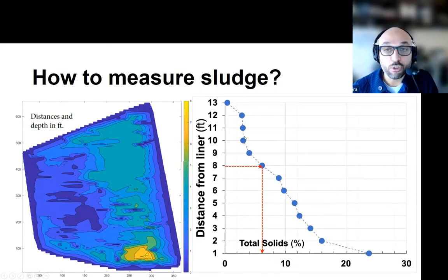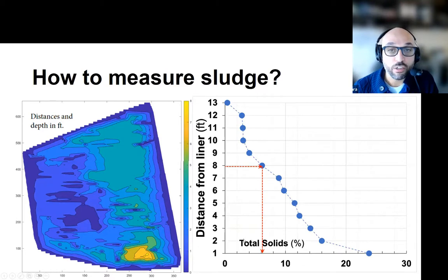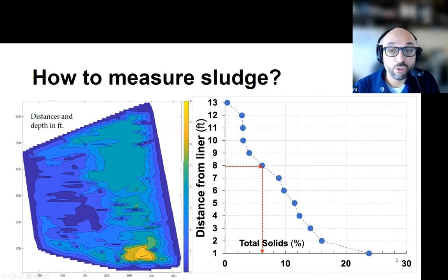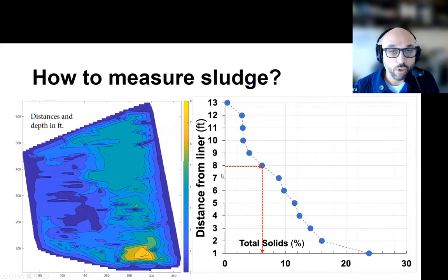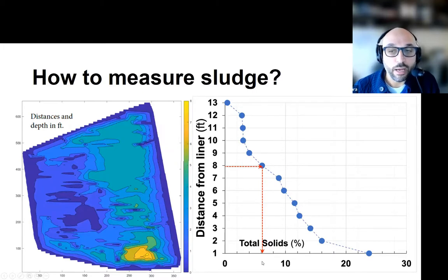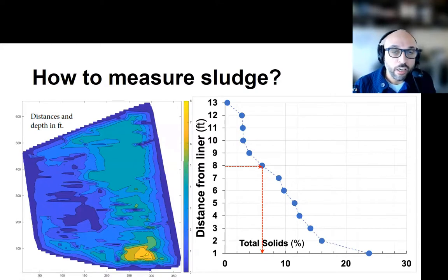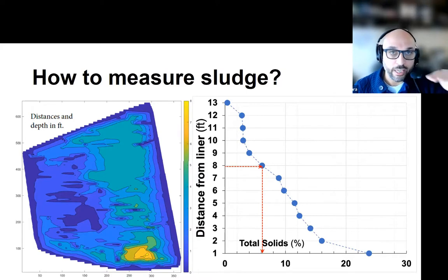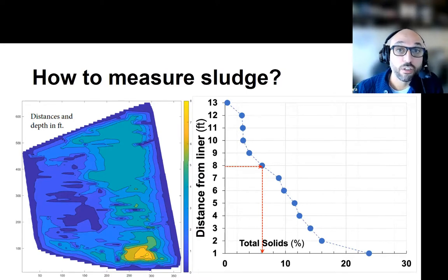Looking at the foot-by-foot solids profile: on the horizontal axis is the concentration of solids from zero all the way to 20 and 30 percent, and the vertical axis is the depth - as you move downward you are moving deeper in the lagoon. Around the eight-foot mark we see approximately six percent solids, and typically the range of six to eight percent is what triggers sonars to indicate that is the depth to sludge.